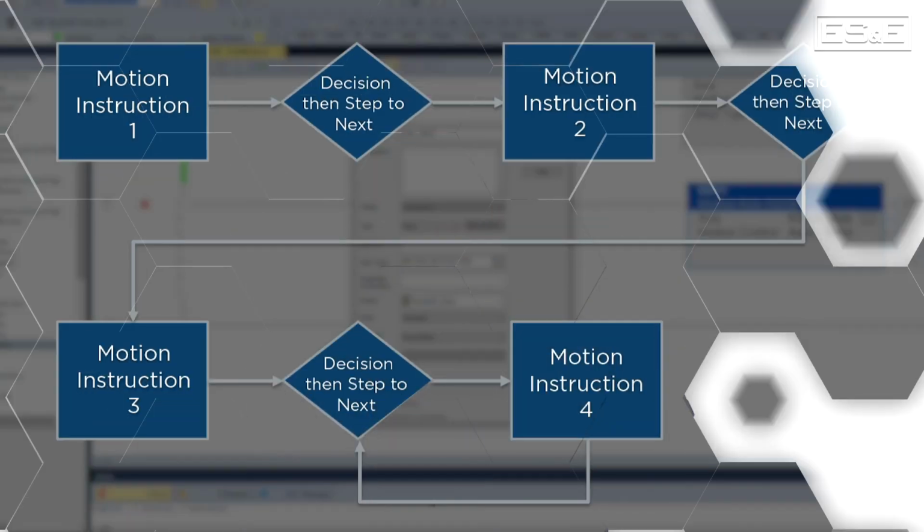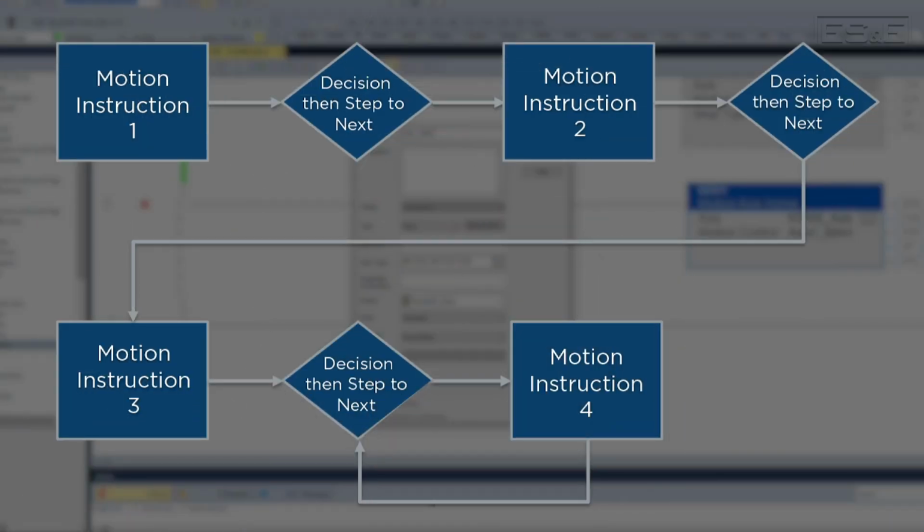However, take care when using these status bits. Newer PLC processors often scan the code so quickly that the motion instructions don't have enough time to fully execute. This is a problem in cases where the same instruction is being used multiple times as part of a sequence. It may be the case that the PC bit is still on from the previous scan, and the sequence will move on before executing the instruction.